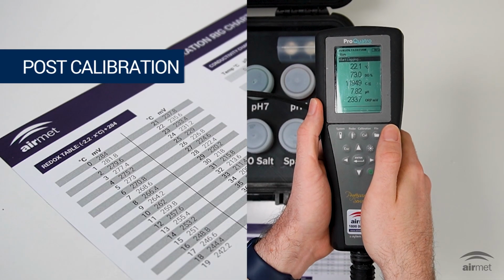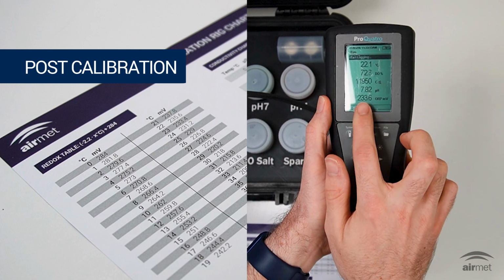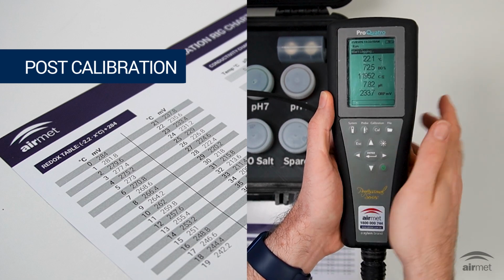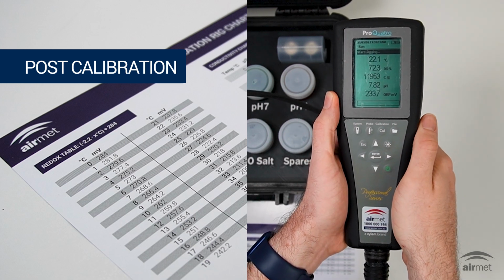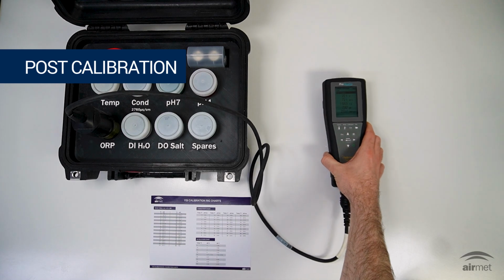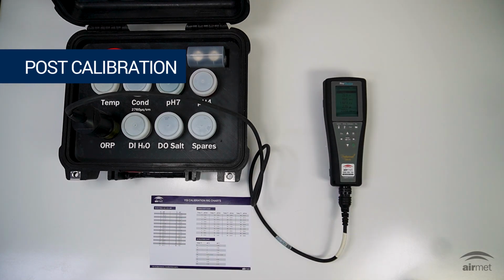After calibrating ORP, always perform a verification check. Check the home screen against the temperature and chart. Accept the calibration once stable and close to the expected value. If the reading drifts or stabilizes slowly, clean the electrode or replace the fill solution if applicable.